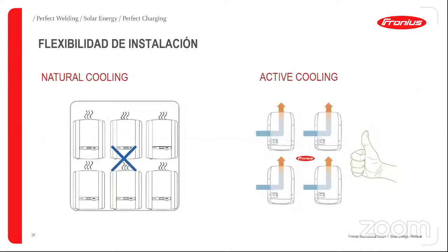Good, and due to this concept, we can also install the inverters very close to each other. That is not allowed in the natural cooling systems that are in our competitors. The difference from our inverters is in the active cooling: we are using fans to control the temperature inside the inverter. The natural cooling concept only relies on the fabric, on the materials of the inverter, but there is never a real control of the temperature inside those devices.